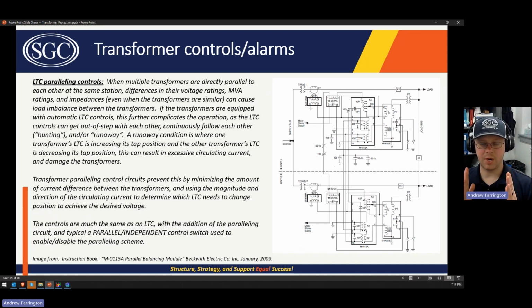If you have two transformers that are in parallel and they both have LTC controls, you want those to operate as a unit, because if, say, the voltage gets too low and an LTC wants to tap up to raise the voltage, well, either LTC may tap up. There's going to be some tolerance there. They're not going to operate at exactly the same time. And you don't necessarily want them to operate exactly at the same time, because if they both tap up, you might get outside of that band and then they both have to tap back down. And that can result in hunting, they call it, where you're trying to always get the voltage back down into the band, where it really wants to be is right on the edge, and it just goes up and down and up and down and up and down, and it causes excessive wear on the LTC.